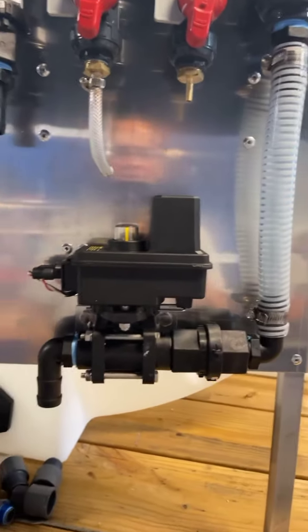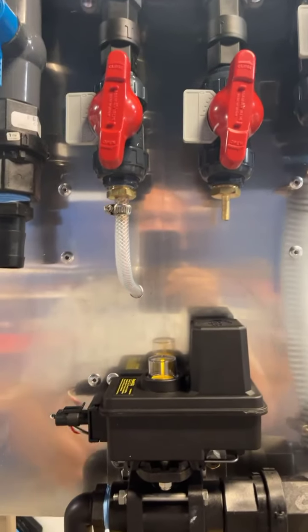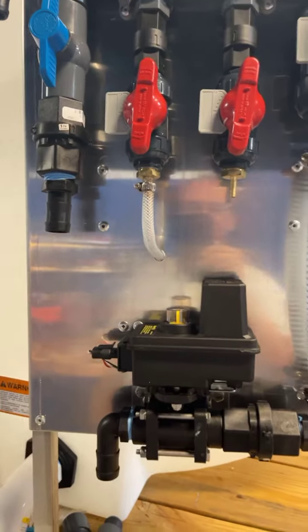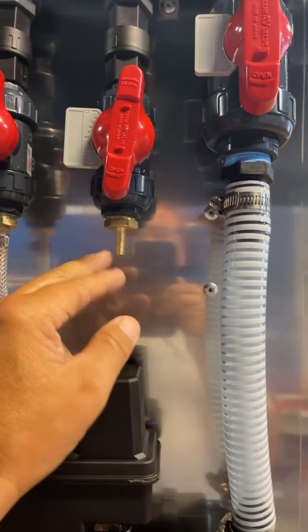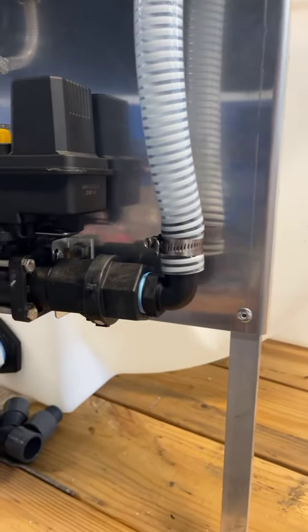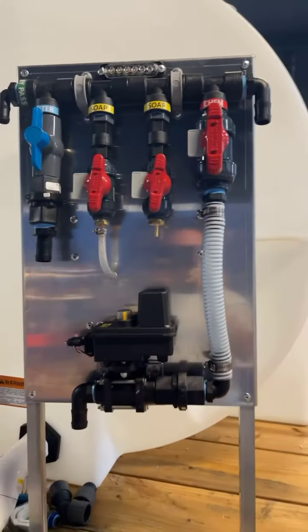The way this one works: you got your bypass here, you got your main water line coming in. What we were having trouble with was figuring out how to line everything up. So Jason — the guy that works for me — he designed this. Your soap connectors are on the back for your solenoid. We're putting brass half-inch down to quarter-inch fittings for your soap so they won't break off — the plastic ones have been breaking. Everything is riveted in, nice and clean. We put the check valve right here so we could have a good clean straight shot going up to the metering valve.